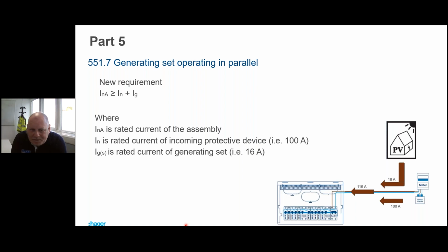So what does that really mean? INA is the rated current of the assembly. So where we've got this assembly, this consumer unit with all the products in it, that's an assembly, and we give that a rating. That usually has a rating of 100 amps. We've then got IN, the rated current of the incoming protective device. So there's our incoming protective device, the service cutout. That could be 63, it could be 80, or it could be 100. So we generally take it at its worst case, 100.